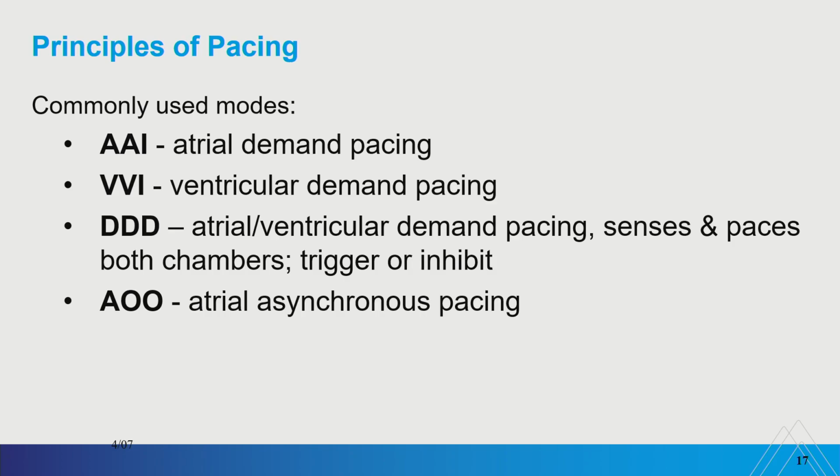170 milliseconds. If there is a QRS, it will sense it, inhibiting itself from pacing by resetting the primary clock. Okay? So you can see that the way I set it up so far is this pacemaker on DDD can A pace at 60 and it can AV pace at 60.